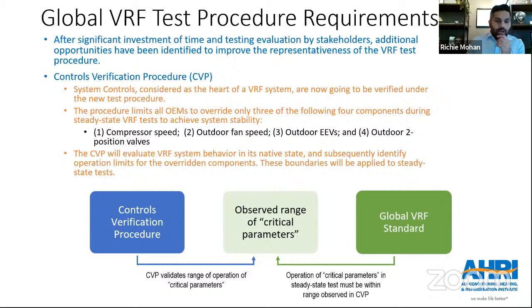And so therefore, the committee realized that we can address this issue by adding what we call a controls verification procedure, because the system controls for VRF equipment are basically the heart of the system. Controls do a lot of the magic in regards to the flow of refrigerant to the indoor units, between indoor units and outdoor units, as well as tackling other important parameters. And so if we can verify whether the controls are behaving in a lab as they would in the field, then we have addressed a lot of the major issues.